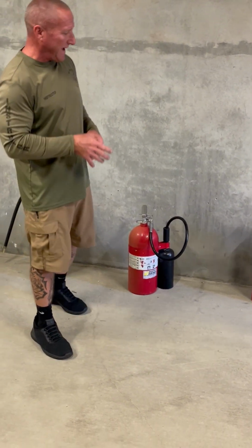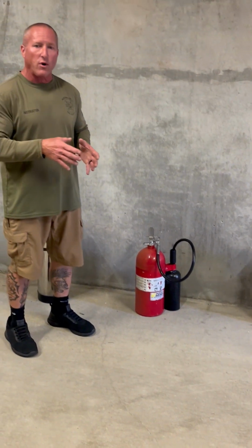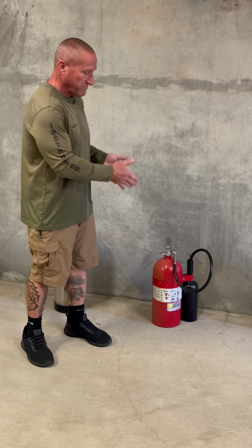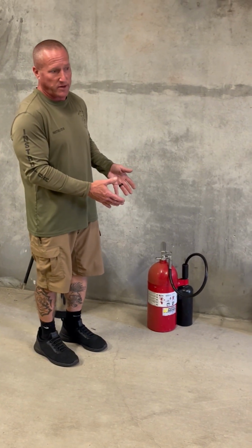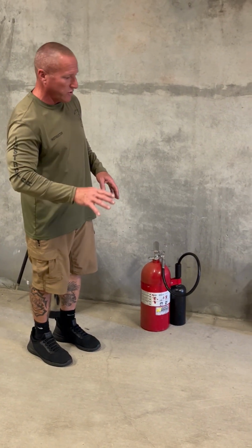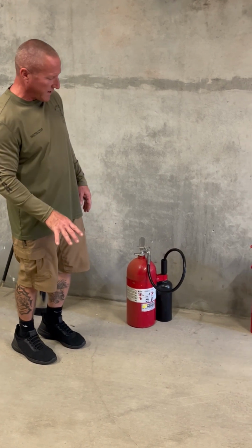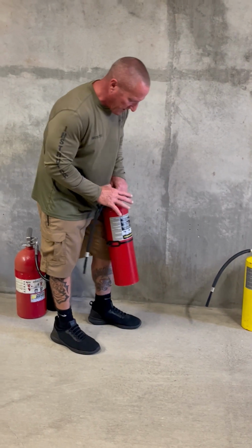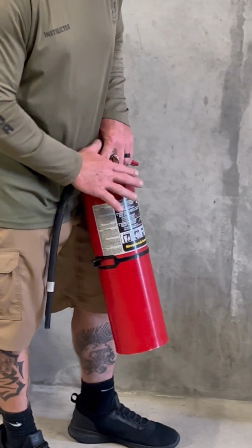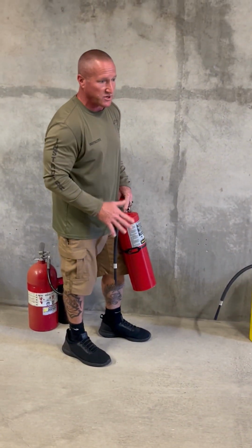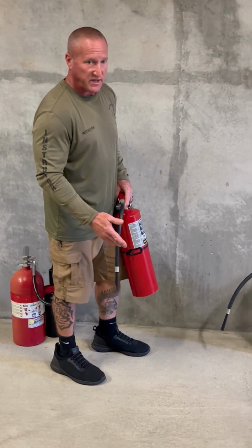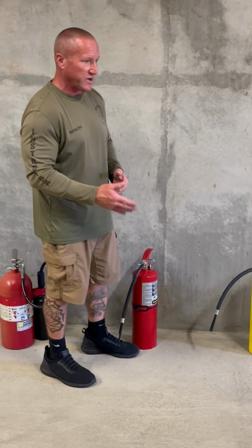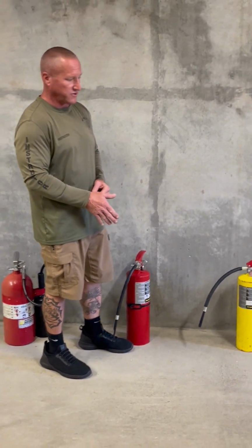Remember, if I'm dealing with a Class C fire, I want to control electric. I want to make sure the electric's off. That makes this basically a Class A fire at that point, or a B fire. So you would take that away. So we want to control the energized equipment. Again, I can use a dry chem extinguisher on my ordinary combustibles. I can also use it on my Class Bs if I need to. For C fires, you can use it too, but again, you must control the electric for that.